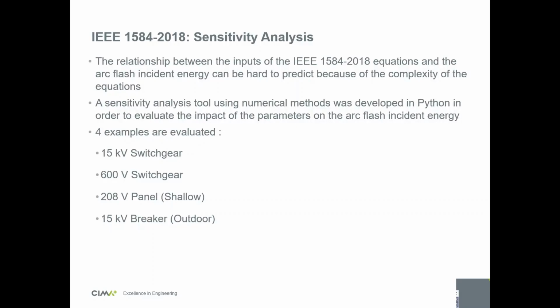So I prepared a tool in Python to do sensitivity analyses for IEEE 1584 2018. It uses numerical methods to find the impact of all the parameters on the final energy. I'm going to show you some examples and some curves of the impact, covering basically all that's within the standard: typical cases for 15 kV switchgear, 600 volt switchgear, a 208 volt panel, which is shallow, and the difference between shallow and not shallow. And then a 15 kV outdoor breaker, for example.